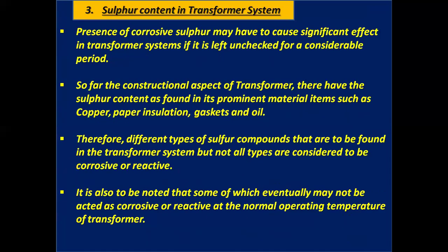Sulfur content in the transformer system. The presence of corrosive sulfur may cause a significant effect in transformer systems if it is left unchecked for a considerable period. In the constructional aspect of a transformer, sulfur is found in its prominent material items such as copper, paper insulation, gaskets, and oil. Therefore, different types of sulfur compounds are found in the transformer system, but not all types are considered to be corrosive or reactive. It is also to be noted that some of them may not act as corrosive or reactive at the normal operating temperature of transformers.